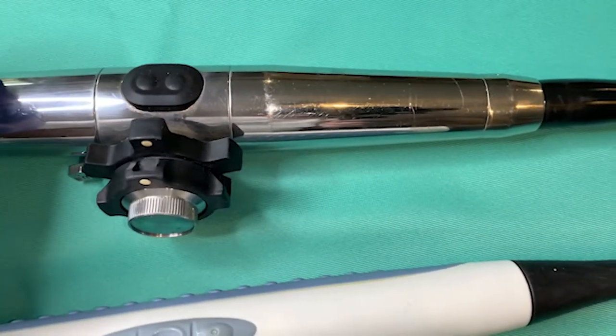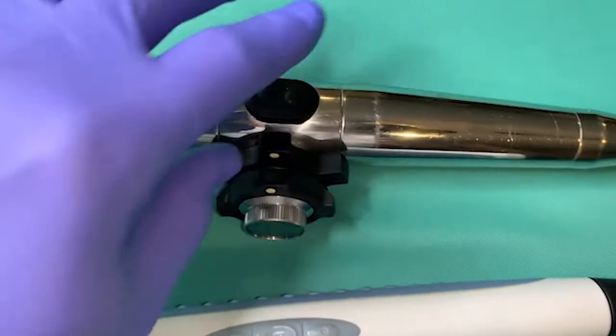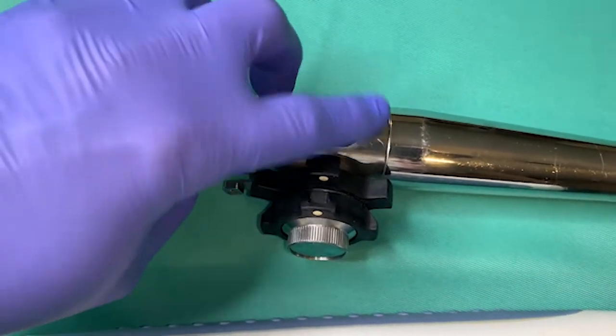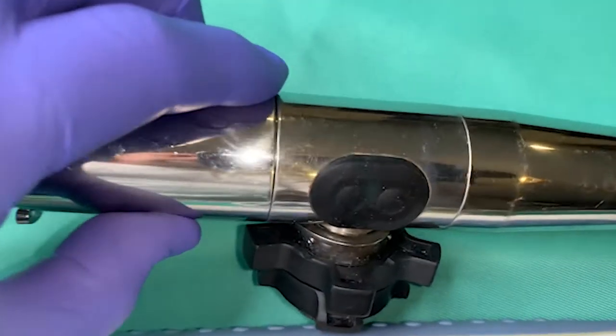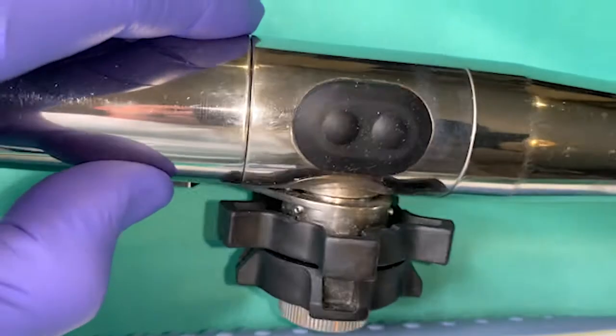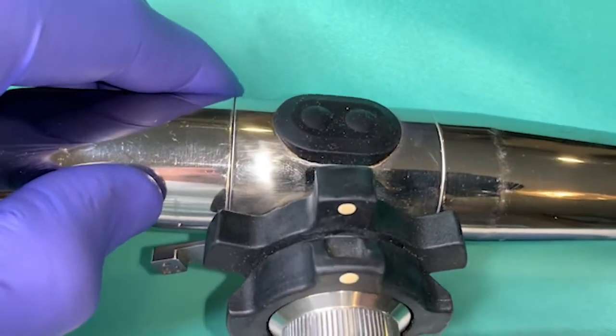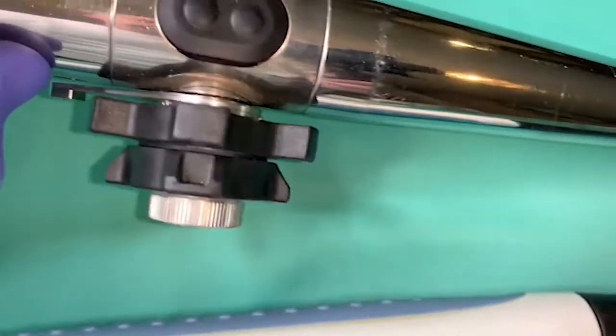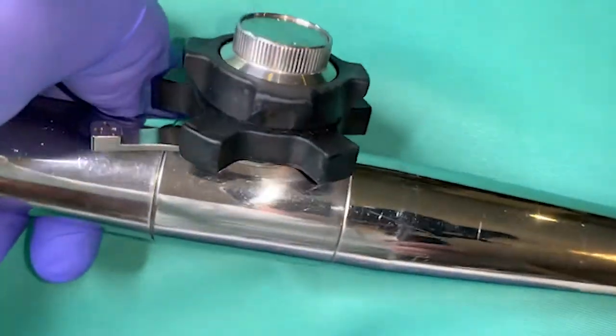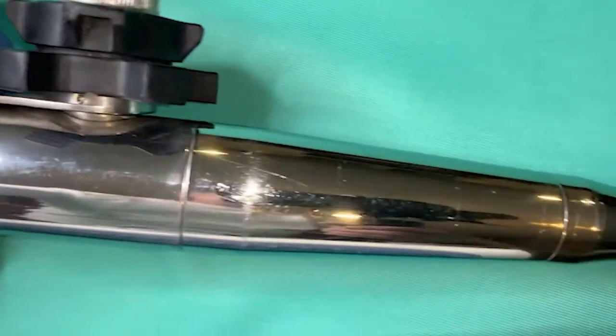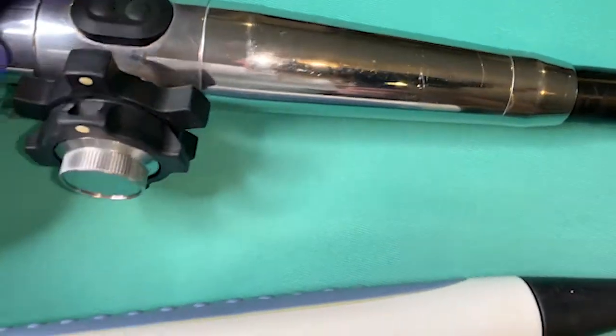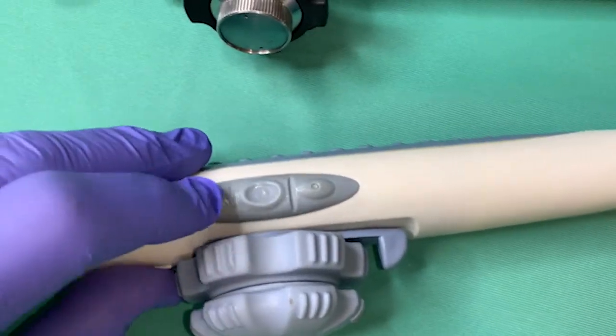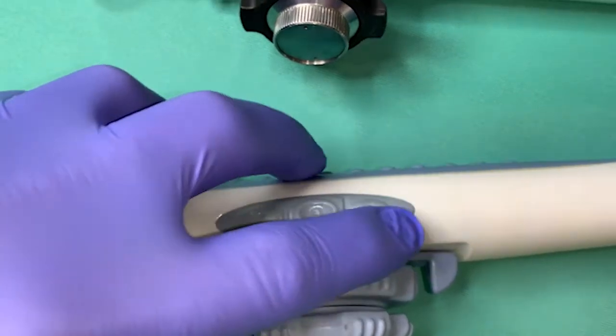Examine the housing looking for dents or cracks. Inspect the switches or rubber switch covers for cracks, tears, or physical damage. Take a look at the angulation control knobs and brake levers for any physical damage. Functional testing of the angulation controls will be performed later. Damages at this location are usually the result of trauma or gross fluid invasion.